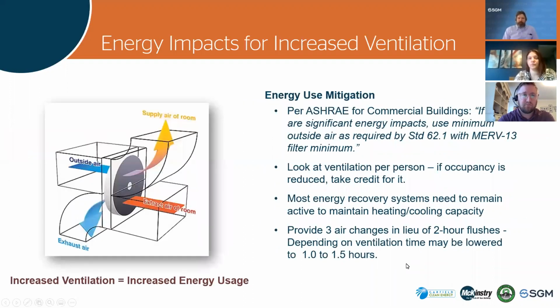Yeah, so, energy use note here. Increasing outside air, increasing ventilation is absolutely going to increase your operating costs, potentially a considerable amount. So in the commercial building guide, there is a statement that says, if there are significant energy impacts, use standard 62.1. So I guess the takeaway would be, look at increasing outside air, but consider the impacts of it and where possible, mitigate that, balance it, I would say, with your operating costs. So we want to increase it, but maybe not to 100%, because that's just not a reasonable ask.